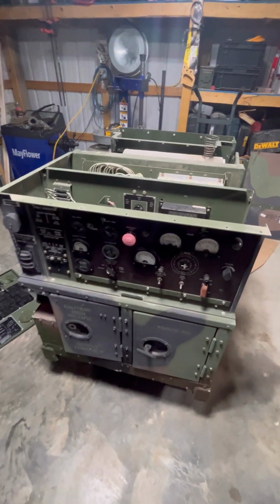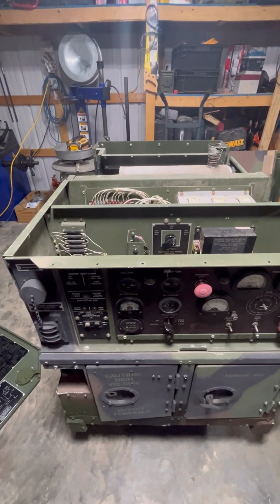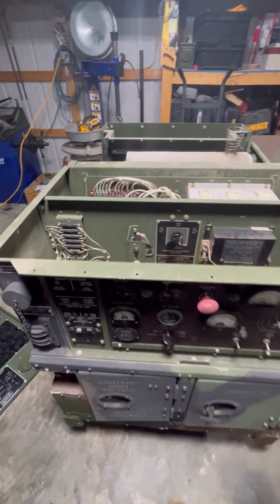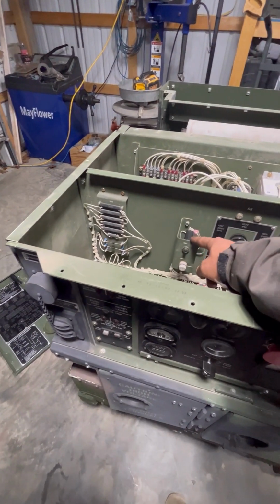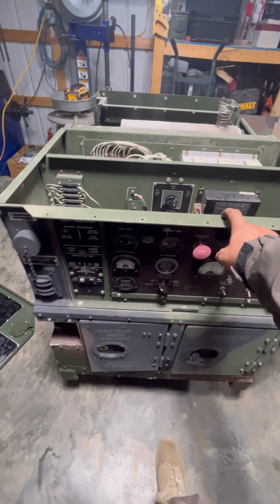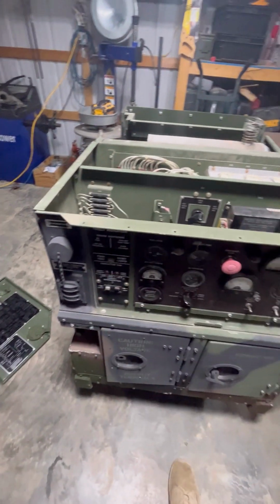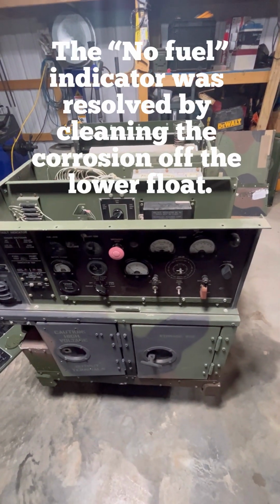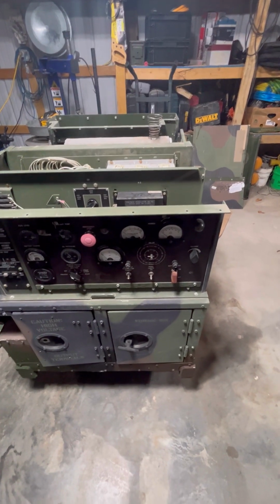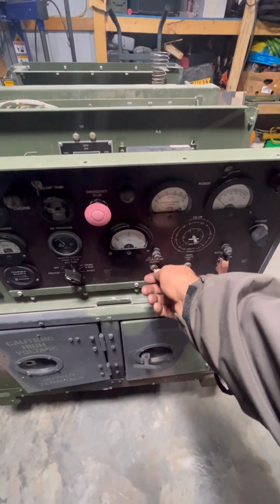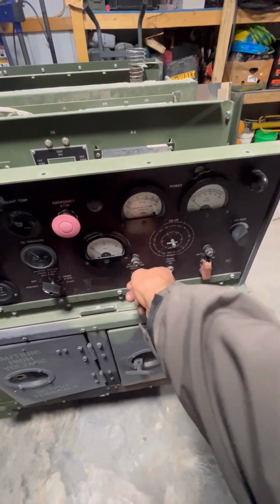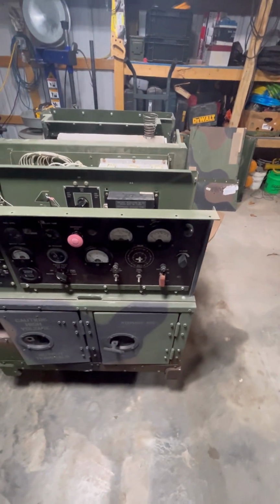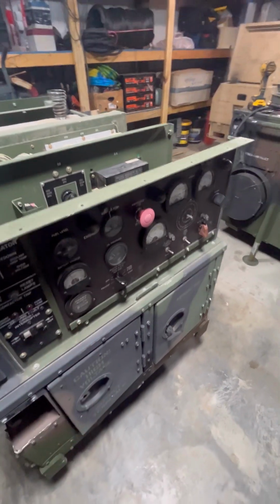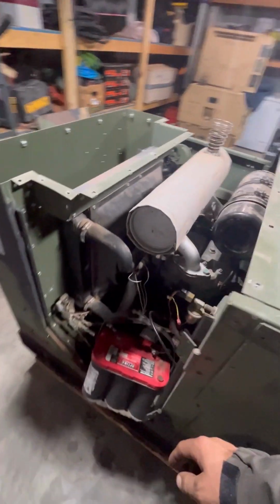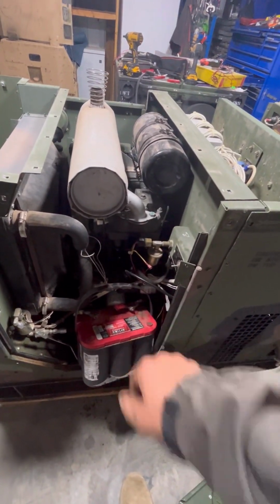All right, that's two issues fixed with the generator. The CB1 breaker is not tripping anymore once the generator is running, and the no fuel light indicator is resolved as well. There are a few more issues I noticed. I noticed that the AC interrupter circuit is not closing, so I'm gonna have to figure out why that is. I'm gonna have to install a new fuel level gauge and finish installing this fuel solenoid back together.